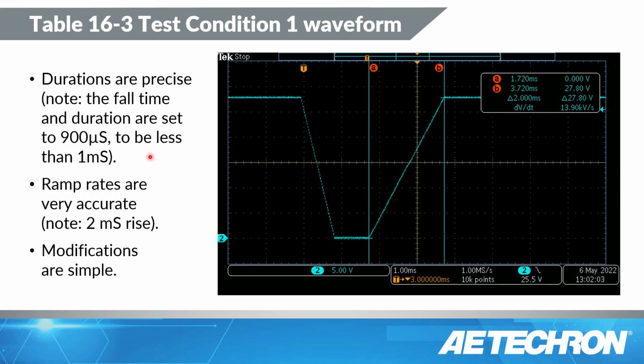But then I have to rise in 2 milliseconds back to full voltage. And you will see here, I put some markers here from this point to this point. If you look at up here, it says the delta time between those two markers is exactly 2 milliseconds. The voltage starts at 0 volts. I've got it just a little bit off the peak there, but it's 27.8, almost 28 volts.